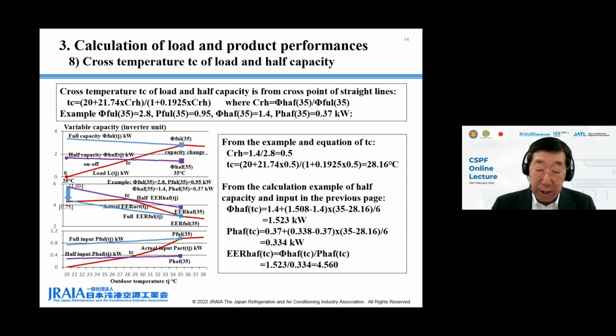This page shows a calculation example of the cross temperature Tc of load and half capacity in the case of 35 degrees C full capacity 2.8, full input 0.95, half capacity 1.4, and half input 0.37 kilowatt. From the equation for the cross point of two straight lines for ISO T1 load and cooling half capacity, cross temperature Tc becomes the equation shown here. CRH in this equation is 35 degrees C half capacity divided by 35 degrees C full capacity, which is 1.4 kilowatt divided by 2.8 kilowatt, equal to 0.5 for this example.